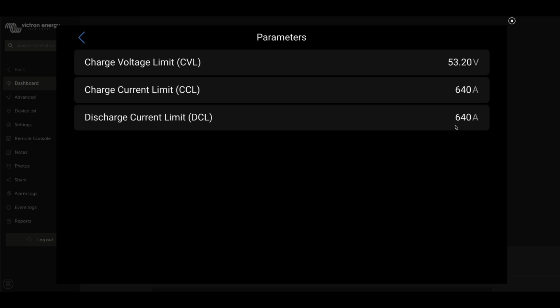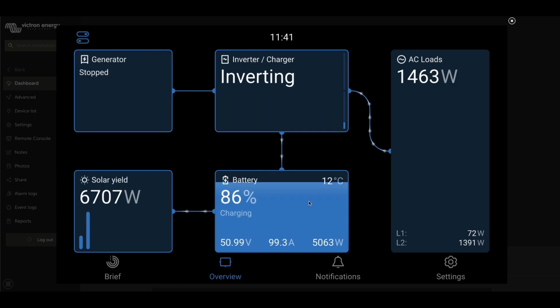The discharge limit, same thing. If you've got a cold battery or a battery that's extremely low voltage and the bank is starting to run out, you may see discharge current limits start to drop. For the most part, in any system that's fully functioning and maintained above kind of a minimum 5% state of charge, your discharge current limit is likely to remain fairly well wide open. Okay, so that's the overall data that you're going to see. This will be what you can see through Victron on-site or with the remote console.